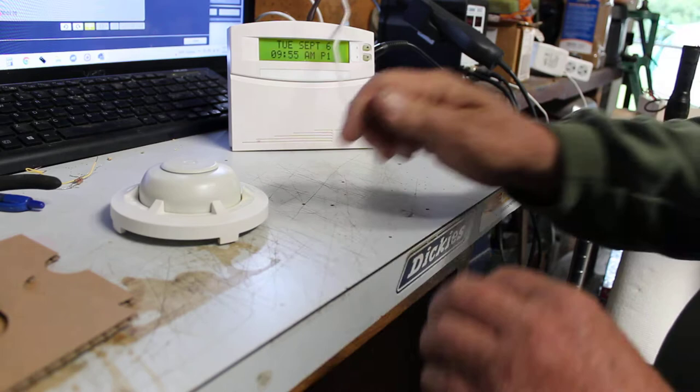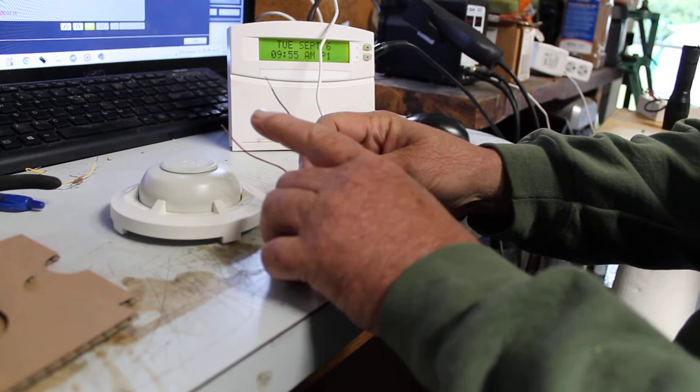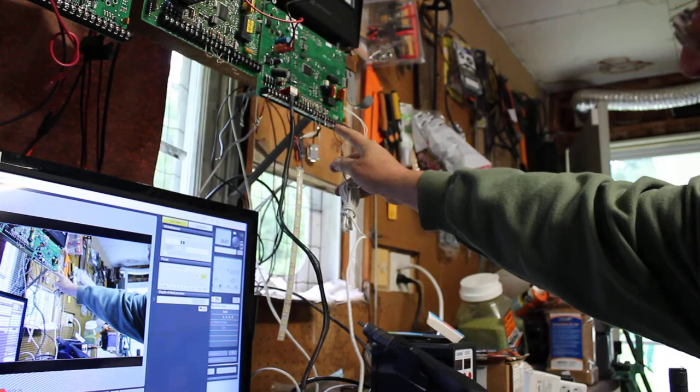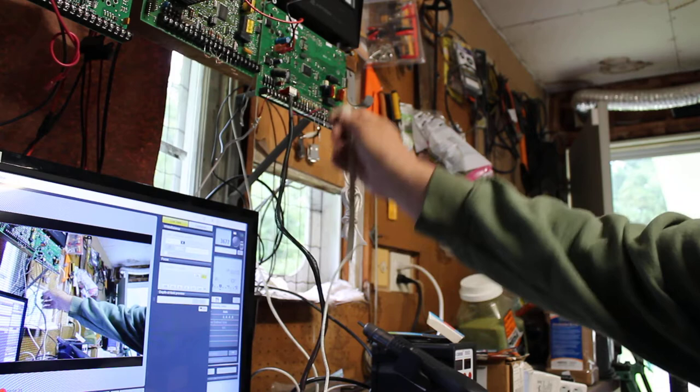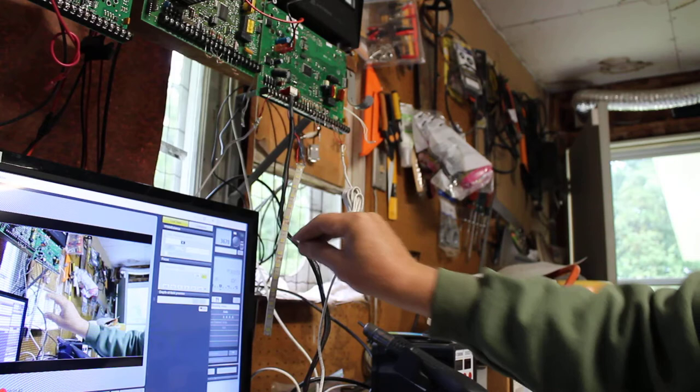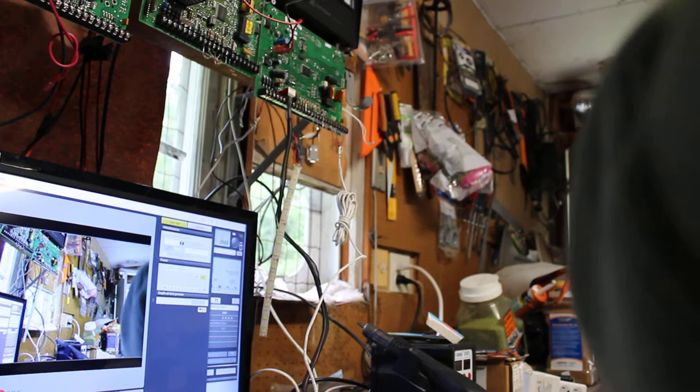Again, it's just a two wire circuit. Right now these are the two wires coming from my control panel which are wired up to zone 8. This is the wire right here and it goes up to zone 8, which is terminals 22 and 24. Right here I got a little LED strip that I have wired into the siren circuit so that when we trip this, it will blink the temporal siren that's coming off the panel for fire.